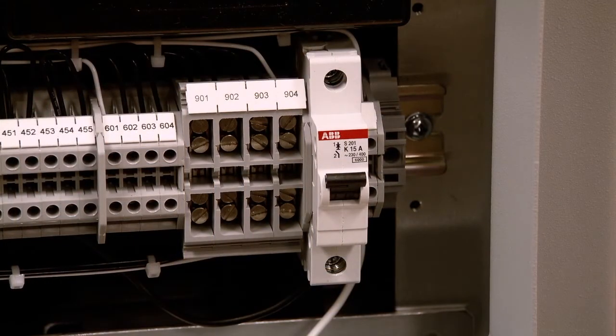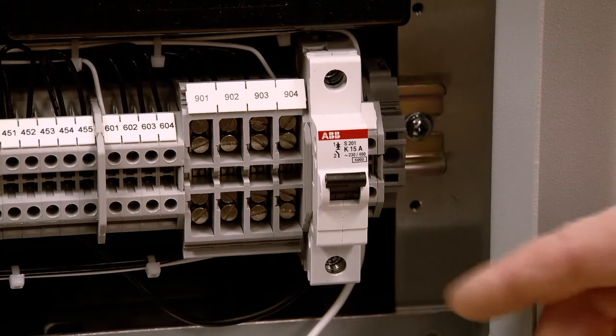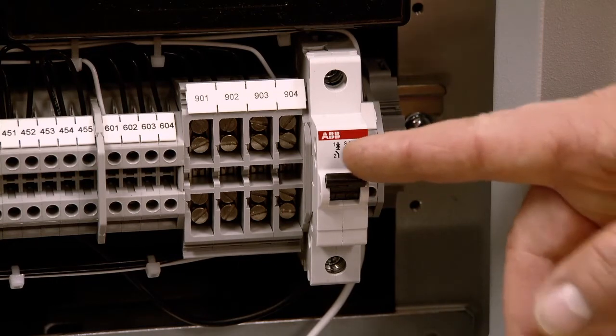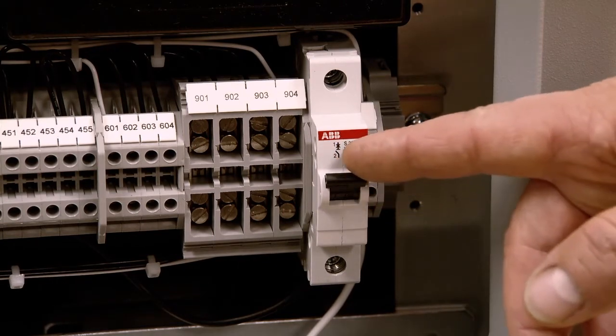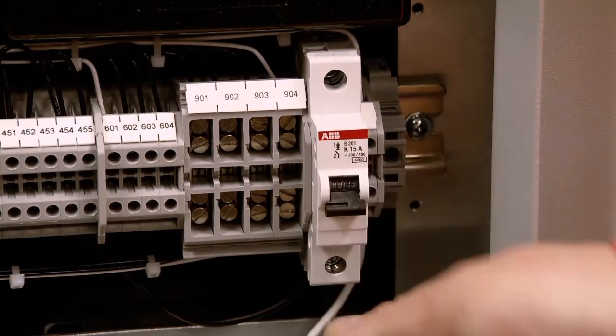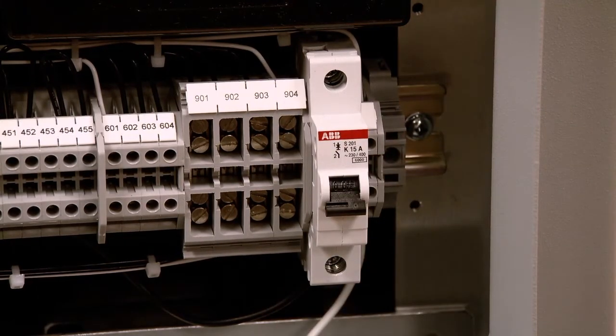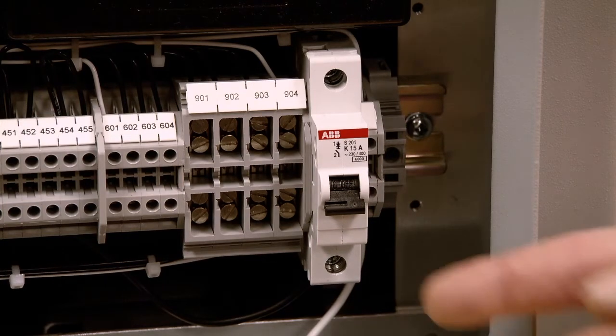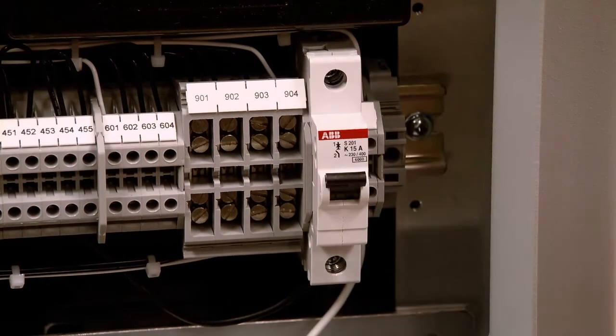The AC for this control comes in through the main breaker seen here. Were this breaker to trip open, this switch would be in the down position. The unit is now still active, but is being supplied from the rear DC battery. As long as a healthy battery is connected, the unit will be active for 24 to 36 hours, depending on weather conditions. To reapply the AC, switch the breaker back to a closed or up position.